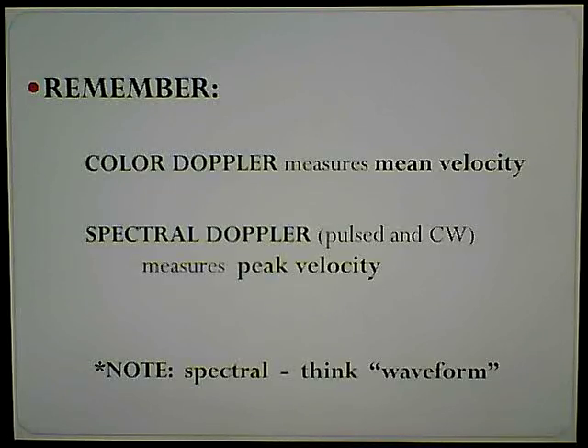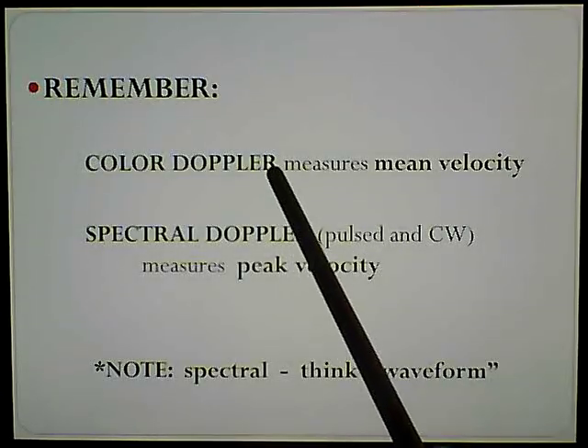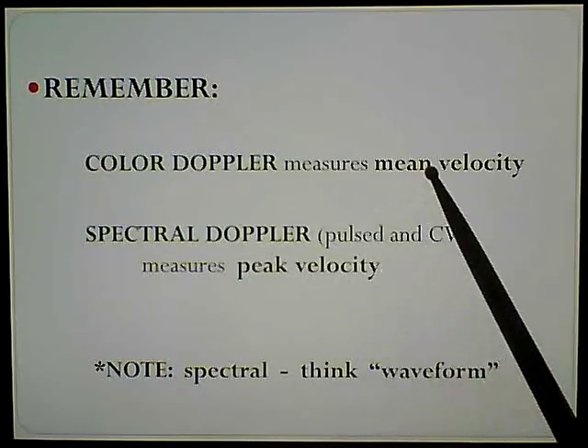Packet size must be carefully selected to balance the two competing interests of color Doppler, which are accurate velocity measurement and adequate temporal resolution - no different from plain black-and-white grayscale imaging. We want a very detailed picture but also very good temporal resolution, so we have to meet in the middle. Remember, color Doppler measures mean velocity - it jumbles them all together and we get an average. Spectral Doppler - pulsed and continuous wave - measures peak velocity, and that's the waveform.